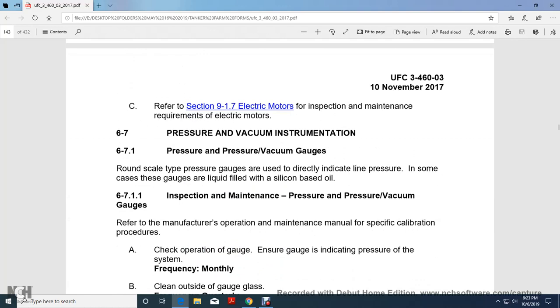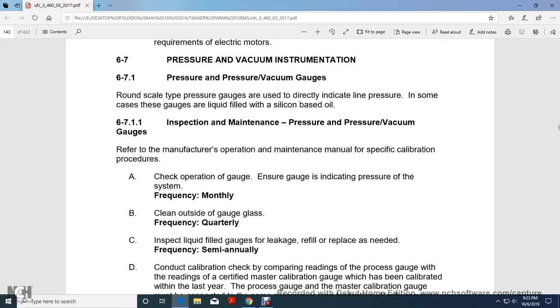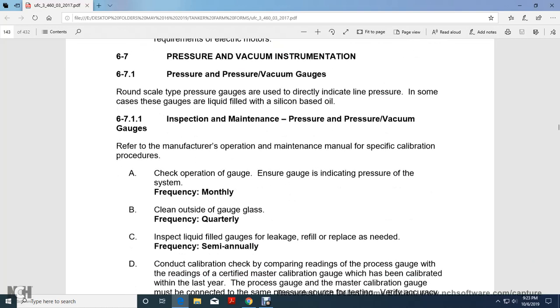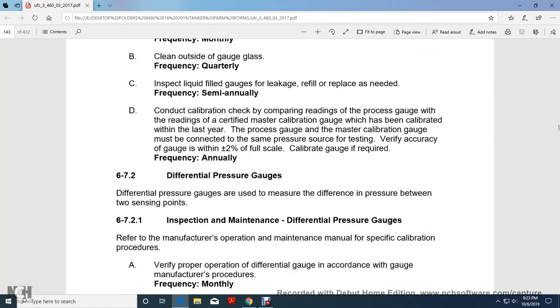Pressure and vacuum instrumentation, pressure and vacuum gauges. Round scale type pressure gauges are used to directly indicate the line pressure, in some cases with the gauge liquid-filled with a silicone base oil. 6-7.1.1, inspection and maintenance of pressure and vacuum gauges. Refer to the manufacturer's operation and maintenance manual for specific calibration. Check the operation of the gauge and ensure it is indicating the pressure for the system, monthly. Check and clean the outside of the gauge glass, quarterly. Inspect liquid-filled gauges for leakage, and refill or replace as necessary, semi-annually.